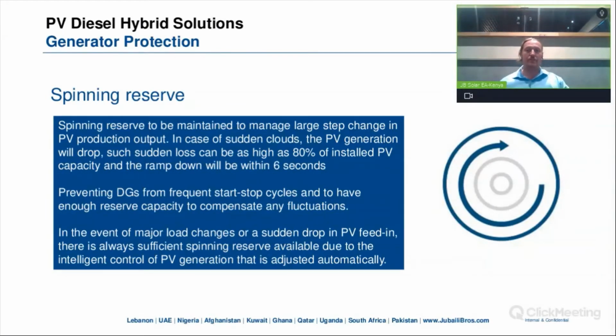And lastly, spinning reserve. So spinning reserve, this is a way to prevent frequent starting and stopping of the diesel generator, because we know that the load will vary very quickly. It will have peaks and valleys, and we don't want the diesel generator to be starting and stopping, and that will damage the diesel generator if it has to start, stop very quickly throughout the day. So spinning reserve allows the diesel generator to have the turbine spinning even though some of that power is not being consumed, and that is to account for the variability of your load. Again, this protects your diesel generator, and it ensures stable power supply to the load. And this is the function of the fuel save controller.